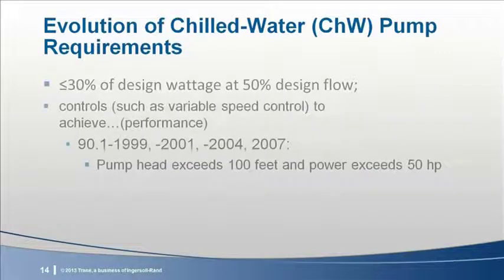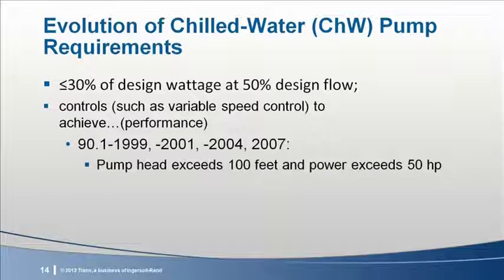In 90.1 1999 through 2007, there was a requirement for the chilled water pump to consume 30% of its design wattage at 50% design flow. Variable speed drives were mentioned as a technology that achieved this performance and were the technology used most often to comply with the standard. It's noteworthy that in these versions of the standard, the requirement only applied to pumps with heads that exceeded 100 feet of design pressure drop and with motors exceeding 50 horsepower.